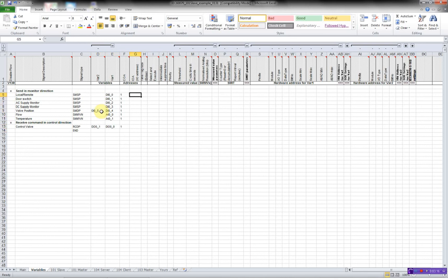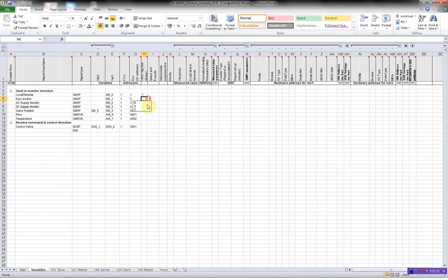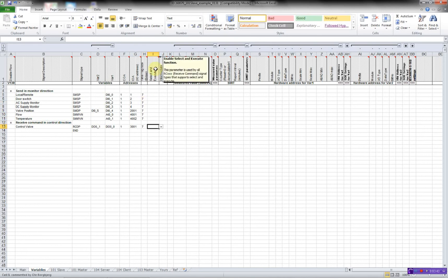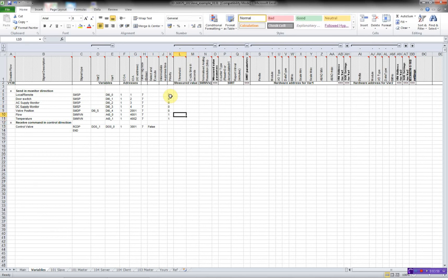Now I have to specify the IOA, starting at one. The time tag size will be seven bytes. For select-execute, we can enable select-execute for commands — we'll just set this to false in this case. For priority, we'll set this for the measured values to one. For measured values configuration, we can put in a threshold for how much the analog value should change before sending a spontaneous message — we'll set five percent, with no cyclic sending.